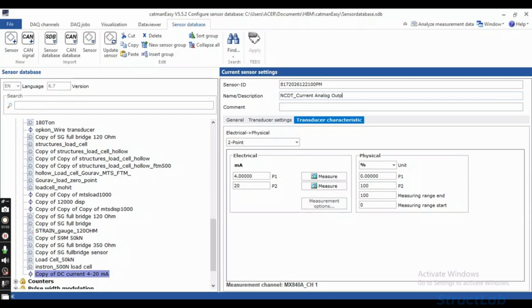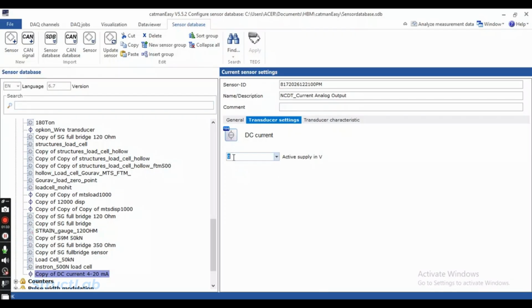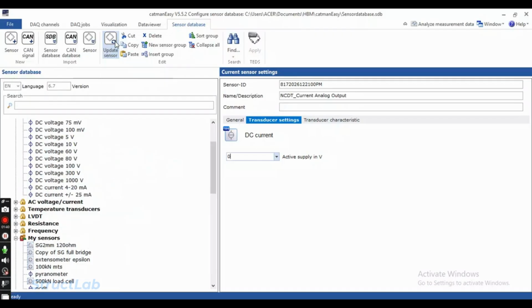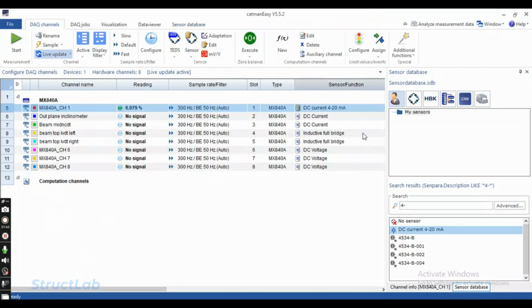Next, move on to the Transducer Characteristic tab to define how electrical signals will map to the displacement change of the NCDT laser under 2-point scaling configuration. Map 4 to 20 mA electrical signals to your corresponding physical displacement range of 0 to 300 mm. Once configured, navigate to the Transducer Settings tab to ensure the excitation is set to 0 volt. Click on Update Sensor to save this sensor profile.